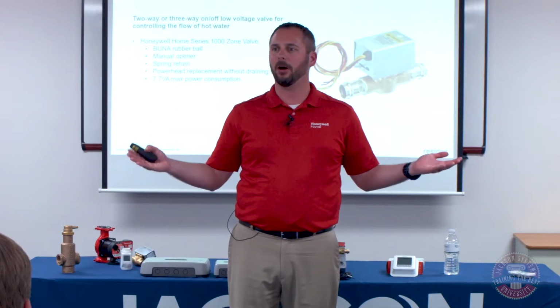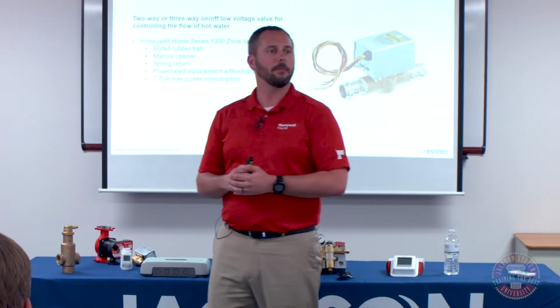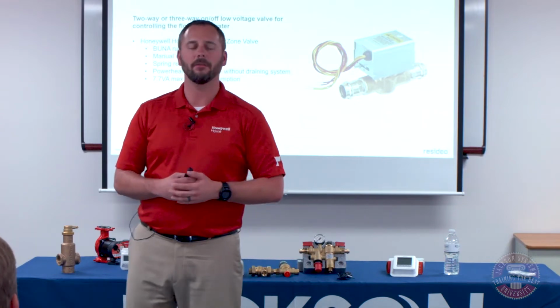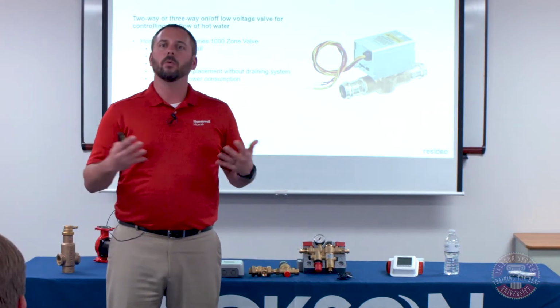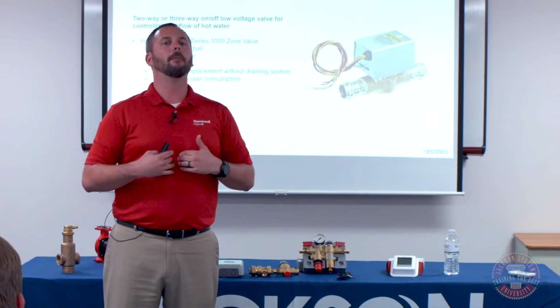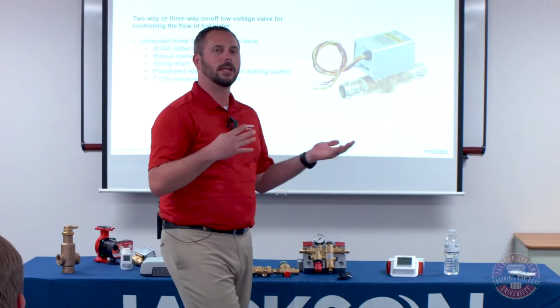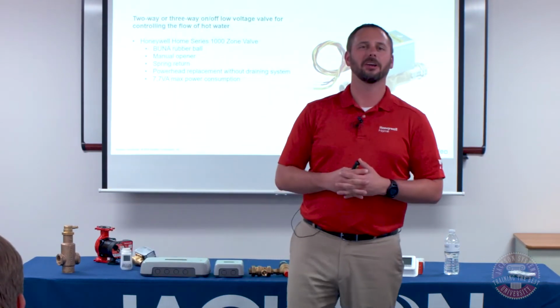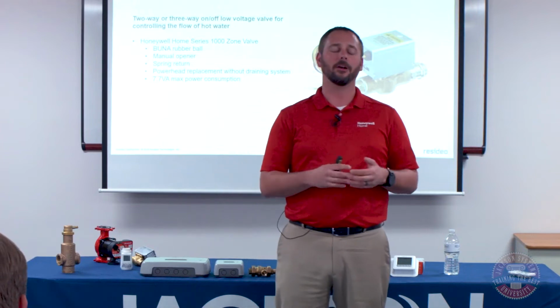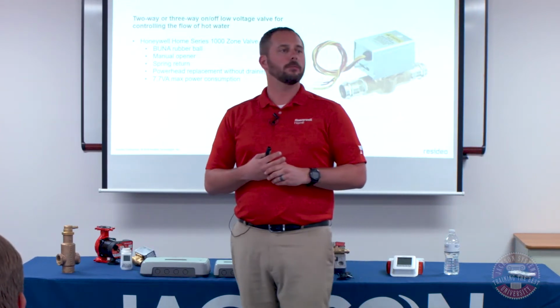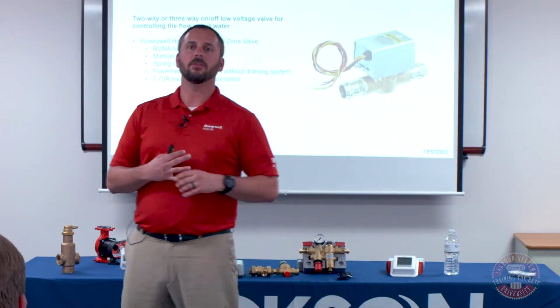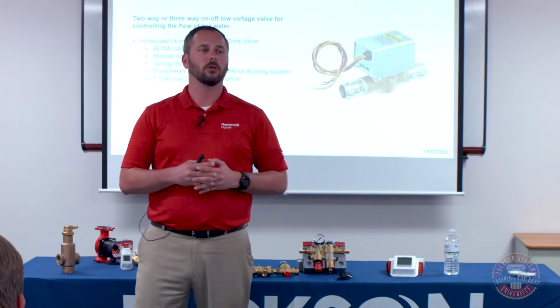Okay, so we talked about pumps. There is the capability of zone pumping, so putting a pump on every single zone. The other thing that we like to see, well, I'm more of a fan of zone valving, truthfully, but again, there's pros and cons, and I could argue that till I'm blue in the face on which one's better. But with zone valves, you get the ability to run one circulator, and these valves draw very, very little power.